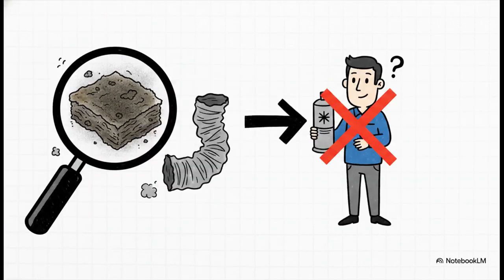So, the absolute crucial takeaway here is this: always, always fix your airflow before you even think about evaluating refrigerant levels. Because dirty filters or collapsed ductwork are usually the actual culprits. So many systems end up receiving completely unnecessary, super expensive refrigerant, all when the real fix was literally just restoring the airflow from the start.